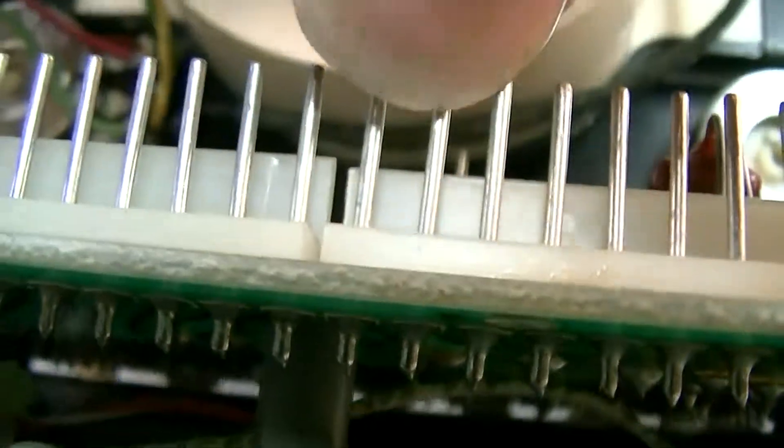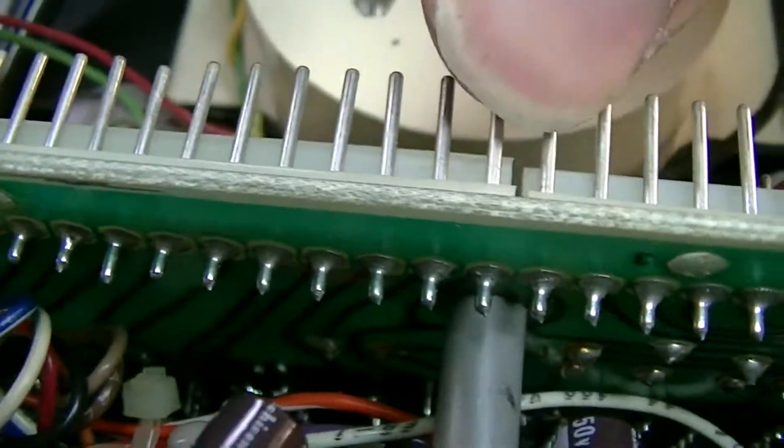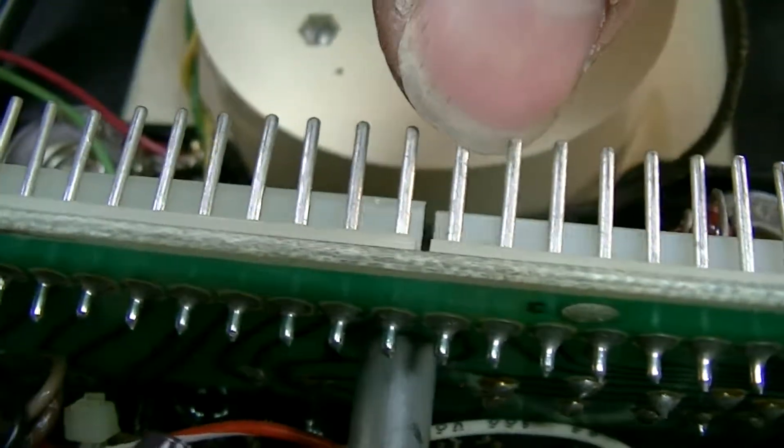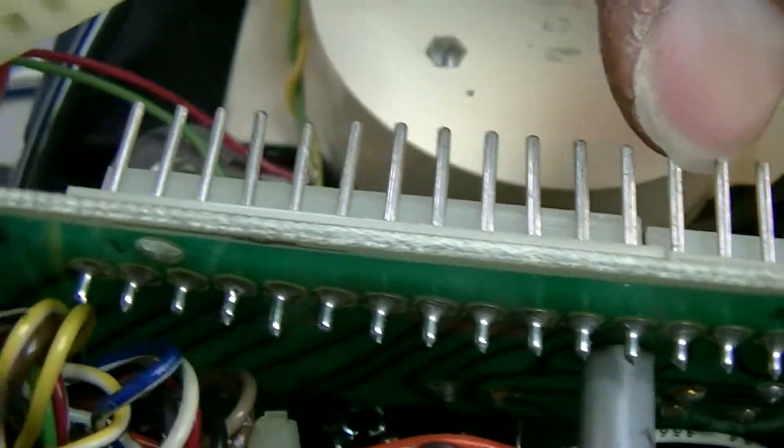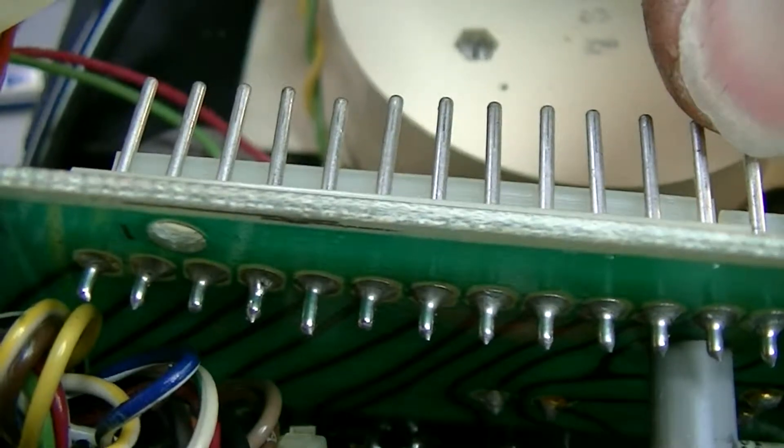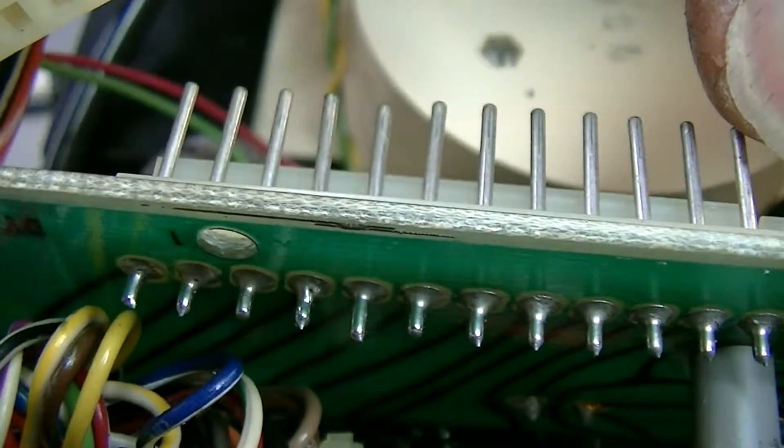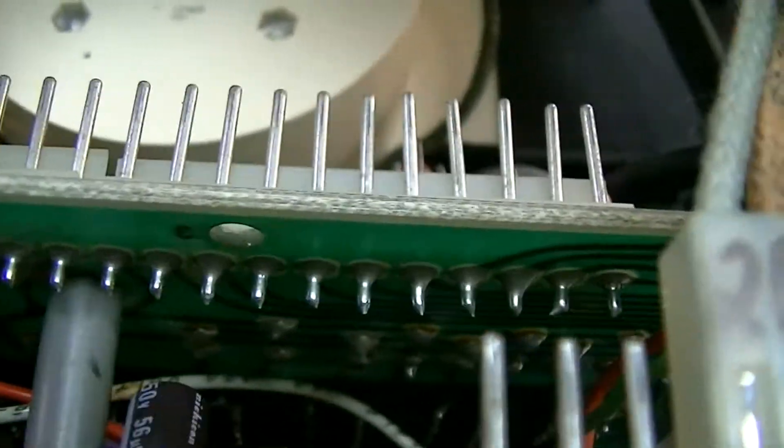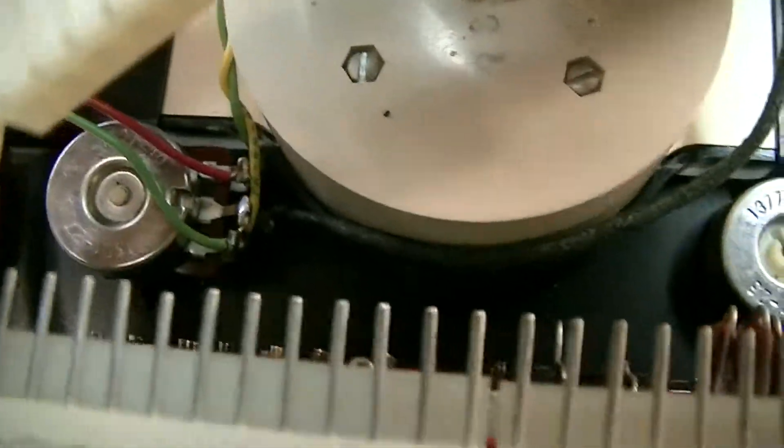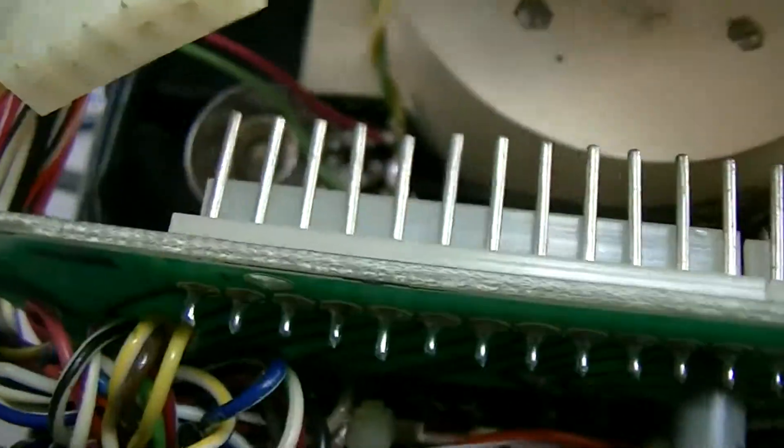I think I'm going to individually pull each board out, re-solder if not every joint, nearly every joint, and see if that makes the thing reliable. And also on this top upper board, I found some joints that were also cracked. You see them right there, it's kind of hard to tell, but right there, there's one. If you look across here, I'll kind of pan across here fairly slowly, you can see cracks all along here.